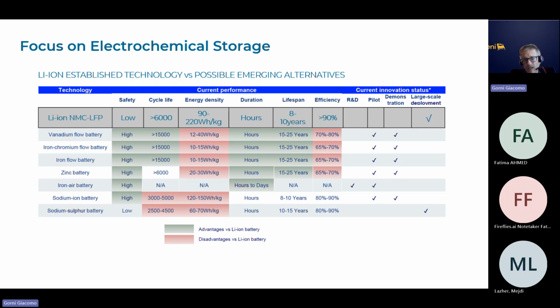electrochemical storage systems are right now the leading technology for energy storage applications, thanks to their interesting, not definitive, cycle life. I mean, 6,000 cycles means that you can use the battery for full discharge and recharge cycles up to 6,000 times without losing too much energy capacity. That means typically the end of life of a battery is reached when you reach 80% of the original nominal capacity. So if you have 1 megawatt hour of storage on a new system, after 6,000 cycles, the manufacturer guarantees that you are still going to have more than 0.8 megawatt hour, okay?